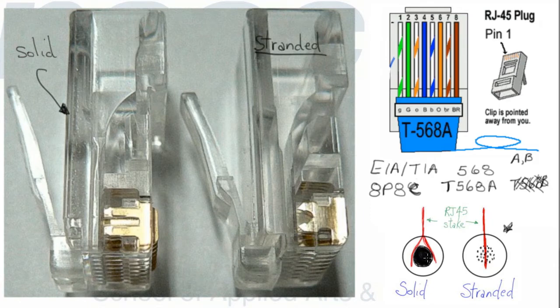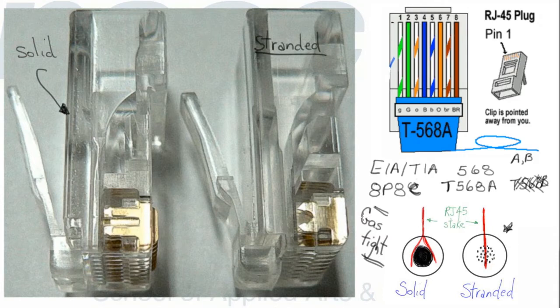In this type, the solid wire is cupped between two prongs, one on each side. The big thing you need to achieve is a gas-tight seal. Gas-tight means that no oxygen molecules will get between the connector and the wire. Oxygen creates oxides, and if you get oxides or rust in between here, it will push those connectors apart. So everything has to be tight enough to make a gas-tight seal.